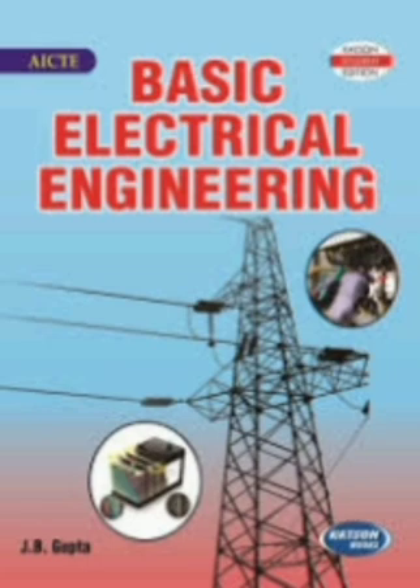The iron loss can be reduced by reducing the core flux density, which means that for the same flux the core cross sectional area must be increased. Size of distribution transformer is larger as compared to a similar power transformer, as the iron to copper ratio of a distribution transformer is higher.